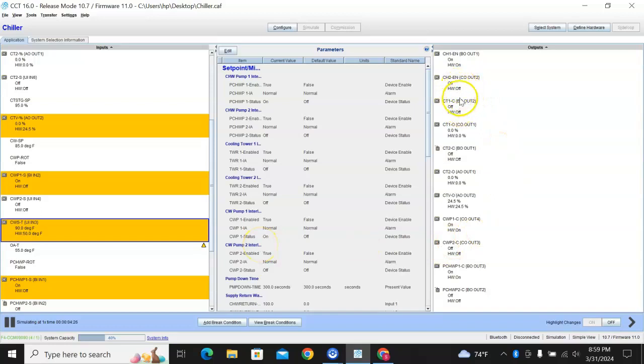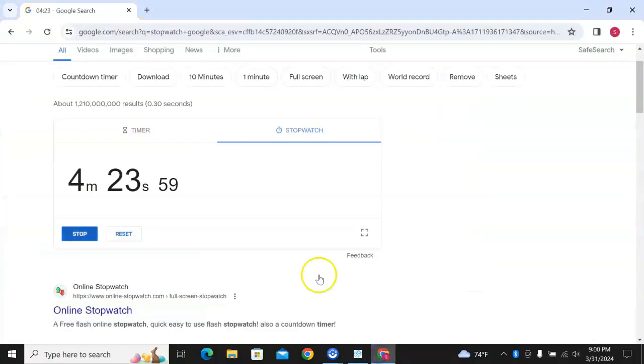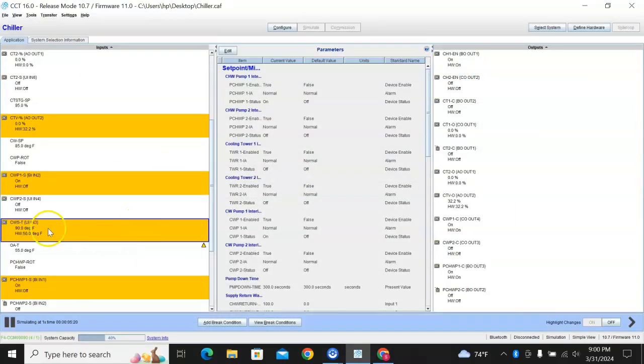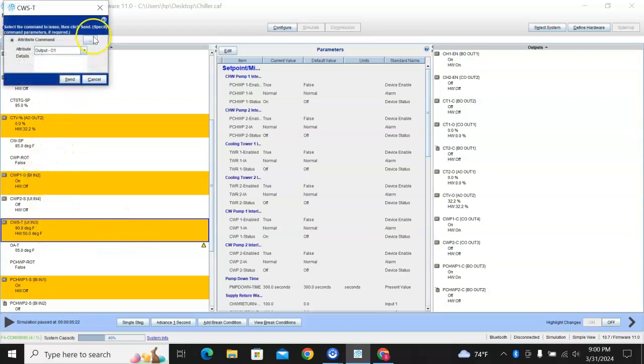And remember, we have not kicked on a fan whatsoever. This is just the bypass valve slowly starting to crack open to go over the tower. 4 minutes in. 5 degrees above. We're about to go 6 degrees above set point.